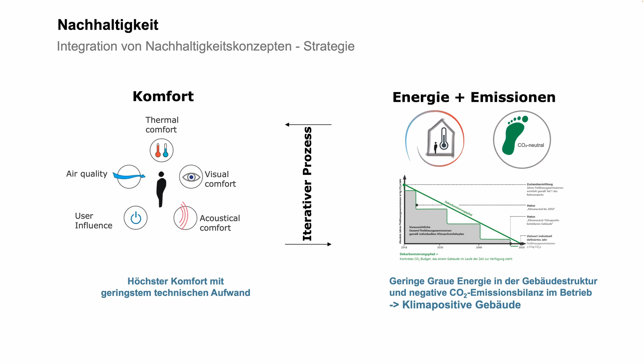If you look into codes and DIN norms, comfort and all these quality aspects are rated—they come in classes. The typical client for a new building says, for me it's easy, I always take deluxe, I want AAA, everything best class. But if you really read, you see class A's temperature range is only recommended for hospitals, not for standard office space. For standard office space, class B is fine. So just ignoring the fact of what type of building you have might bring the emissions up.